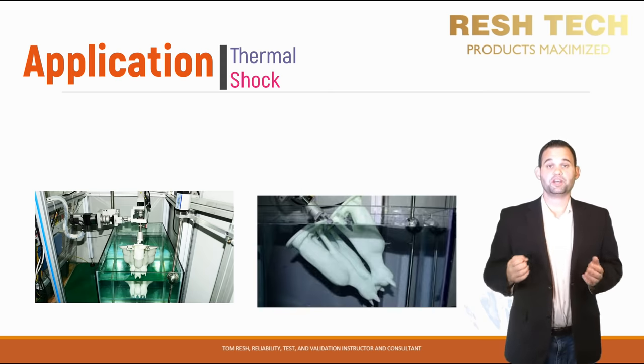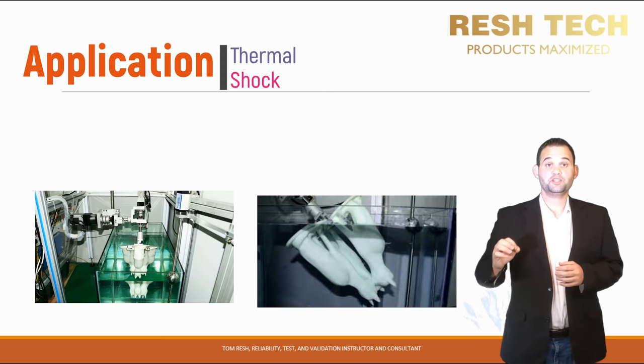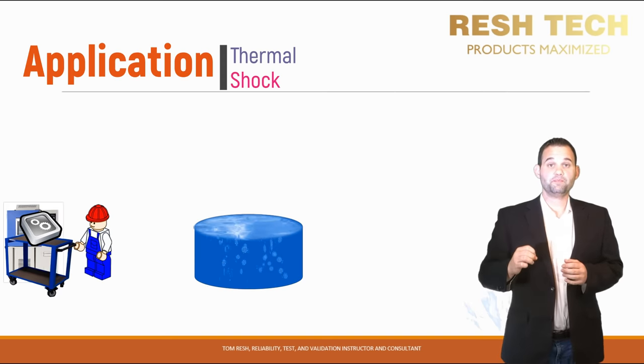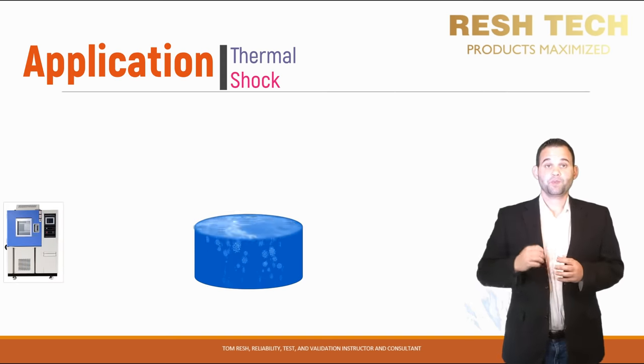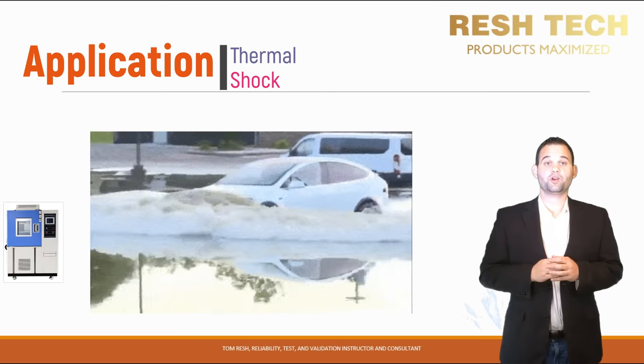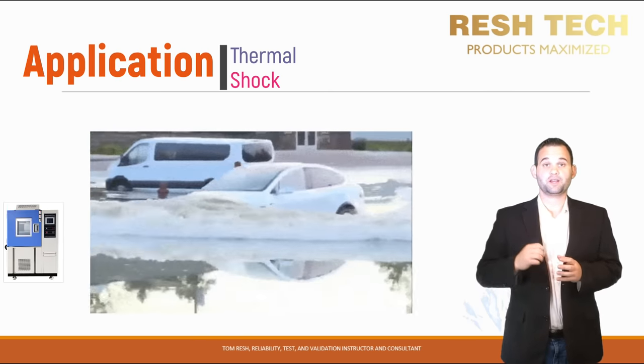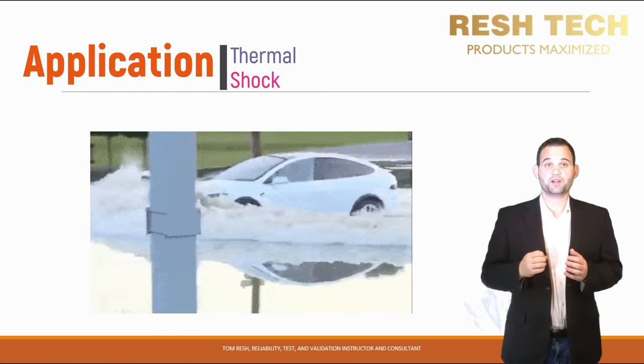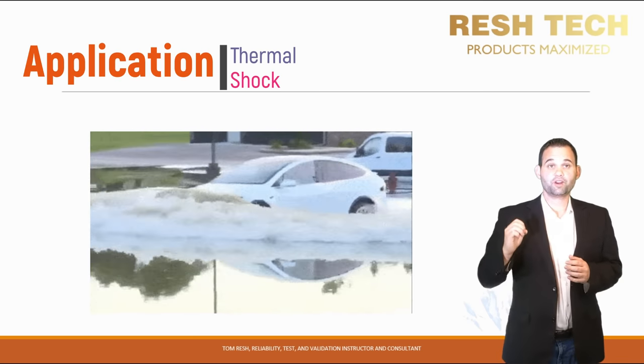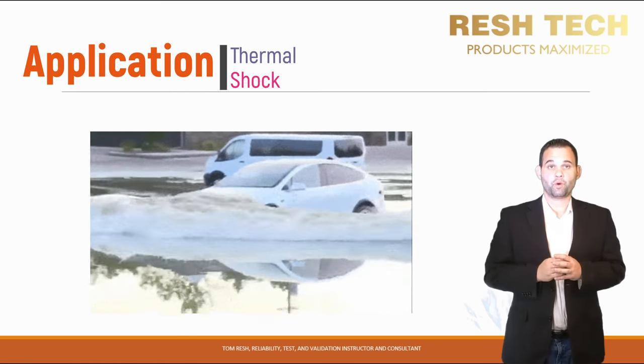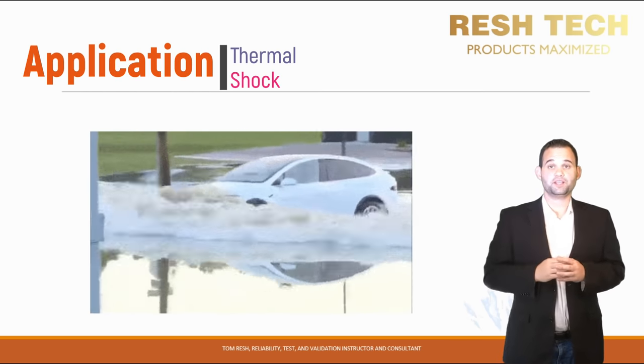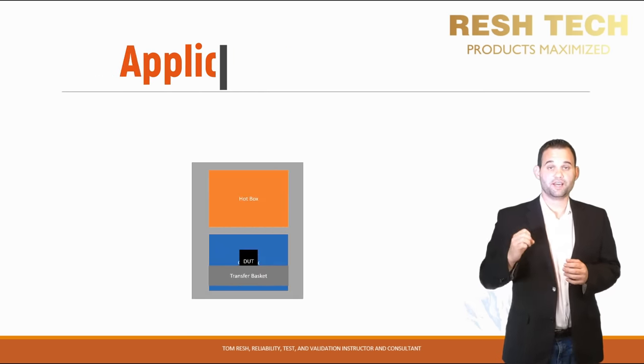The third type is the hybrid thermal shock test, which can consist of air heating in an oven followed by immersion in an ice bath, as an example. This has practical applications especially in the ground vehicle industry, where a vehicle may be stored in a warm garage overnight, driven out into a cooler environment, and perhaps crosses a shallow stream or deep puddle of cold water — causing the part or vehicle to be thermally shocked. There are standards that call out immersion tests requiring preheating the system prior to immersion in cooler water, including MIL standard and ISO specifications. For most applications, air-to-air thermal shock will be the way to go.